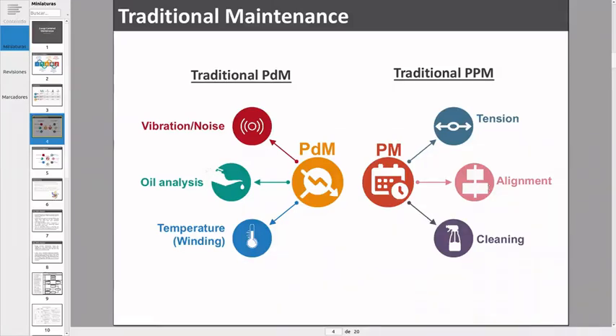We need to switch it off because we need to clean it and replace parts, so the machine will not be serving its objective. If it's a server room with one air handling unit serving it, we can't simply shut it down. We have to get an alternative machine to supply air to that area, then do the maintenance. That's why planned preventive maintenance sometimes tends to be more costly than expected, because of the application and the need to switch it off.